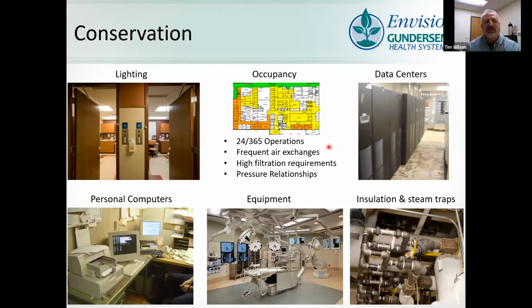So there always seems to be a lighting project where you can go back in and get big savings. Occupancy is huge — going into your building, understanding what areas you're running and when, and if they're not running, making sure you've got building automation to shut them down. We had HVAC tech just last year find about $20,000-$30,000 worth of occupancy settings in our hospital, which is one of the most efficient hospitals probably in the nation. He's still able to find occupancy issues in a building that's already really good, so there are always opportunities to dial it in tighter.